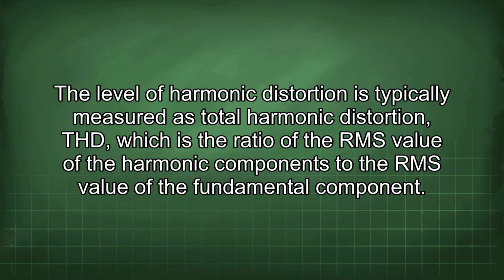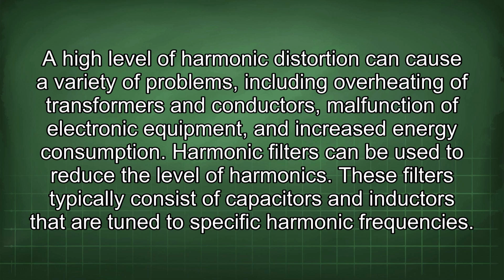The level of harmonic distortion is typically measured as total harmonic distortion, THD, which is the ratio of the RMS value of the harmonic components to the RMS value of the fundamental component. A high level of harmonic distortion can cause a variety of problems, including overheating of transformers and conductors, malfunction of electronic equipment, and increased energy consumption. Harmonic filters can be used to reduce the level of harmonics. These filters typically consist of capacitors and inductors that are tuned to specific harmonic frequencies.